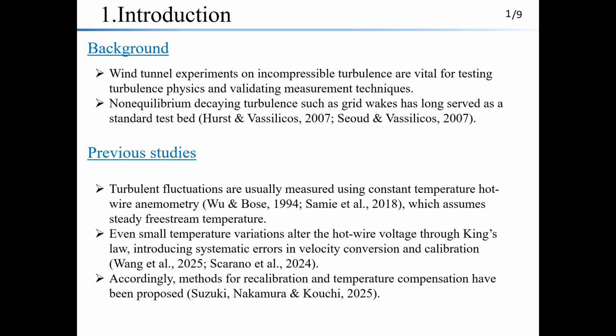Turbulent fluctuations are commonly measured using constant temperature hot wire anemometry, which assumes a steady freestream temperature. Even small temperature variations modulate the hot wire output voltage through King's law, introducing systematic errors in velocity conversion and calibration. Accordingly, methods for recalibration and temperature compensation have been proposed in 2025.